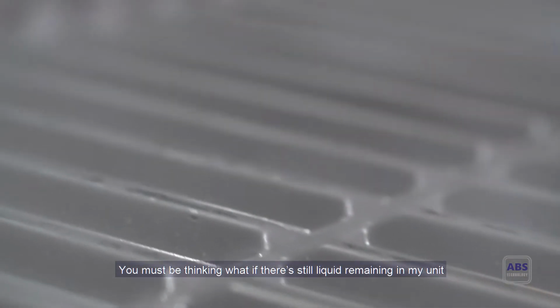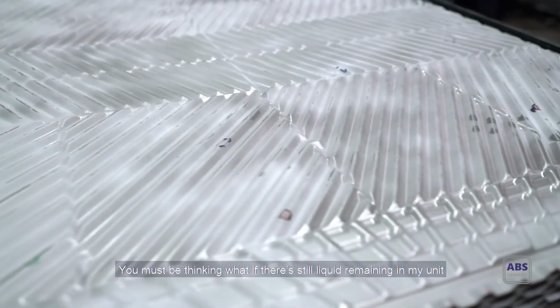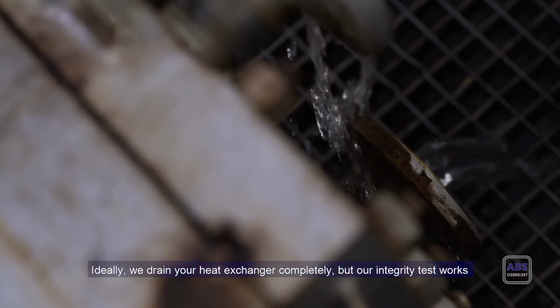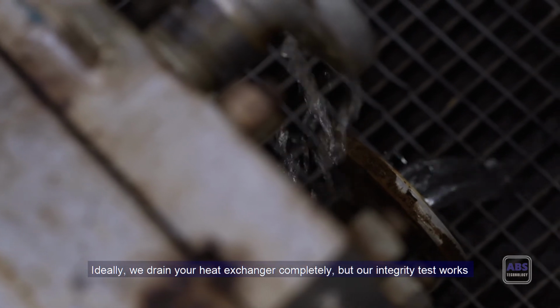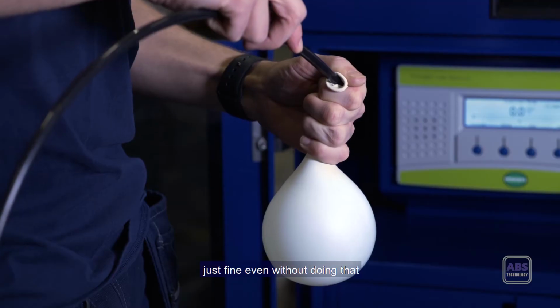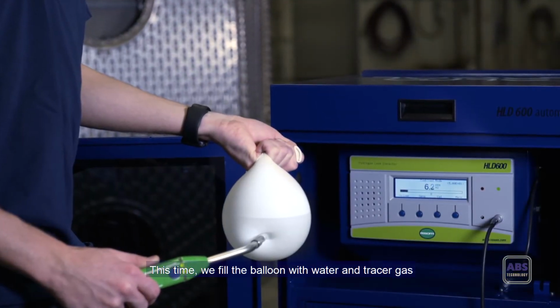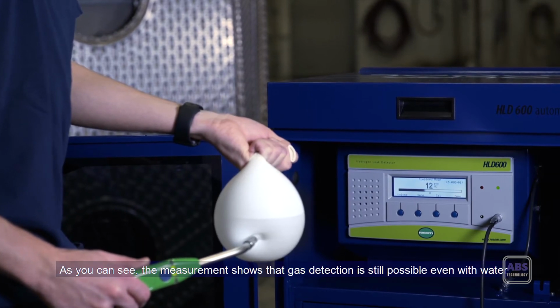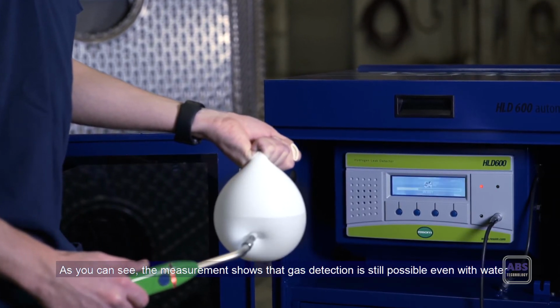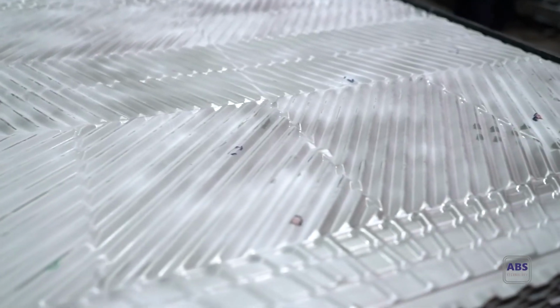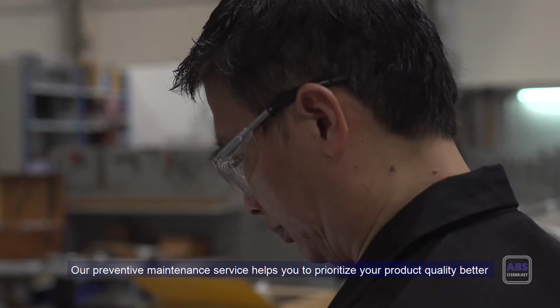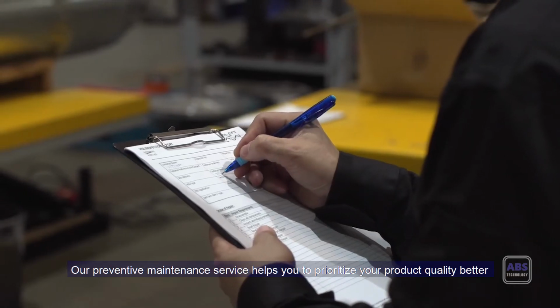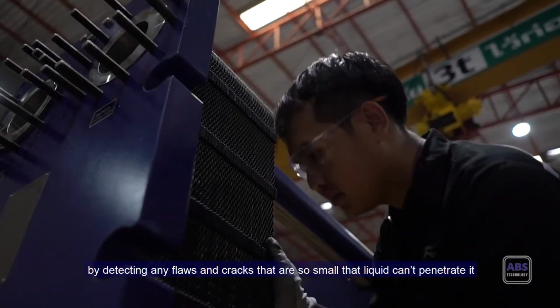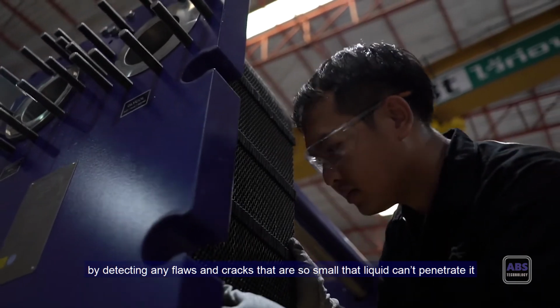You must be thinking, what if there's still liquid remaining in my unit? Ideally, we drain your heat exchanger completely, but our integrity tests work just fine even without doing that. This time, we filled the balloon with water and tracer gas. As you can see, the measurement shows that gas detection is still possible even with water. Our preventive maintenance service helps you prioritize your product quality better by detecting flaws and cracks so small that liquid can't penetrate them.